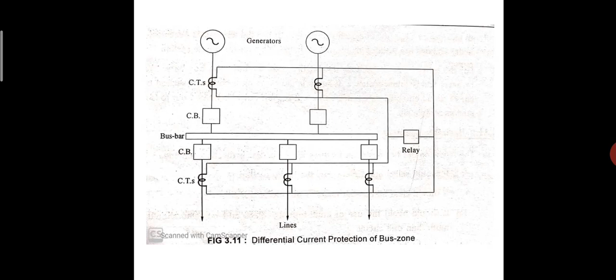A simple differential protection of a bus section. The busbar is fed by generators and supplies load to three lines. The CTs are connected in each circuit connected to the busbar. The secondaries of these CTs are connected in parallel. The protective relay is connected across this parallel connection. All CTs must be of the same ratio in this scheme, regardless of capacities of various circuits.